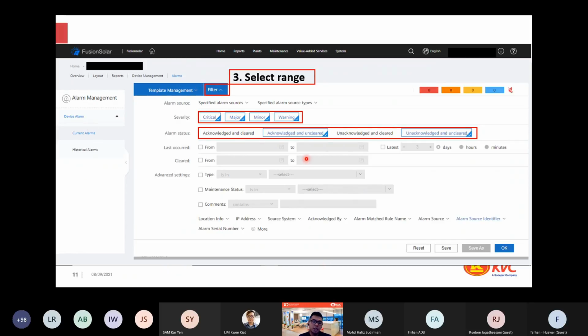Once you're in the alarm page, you need to filter the range. My common approach is to just click on every single thing: has it been acknowledged, has it been cleared, or is it still an open alarm. I'll click on every single thing and filter. Then you can divide it by when's the last occurrence, when is it cleared. You can choose what date, what month, or what duration you're looking at.